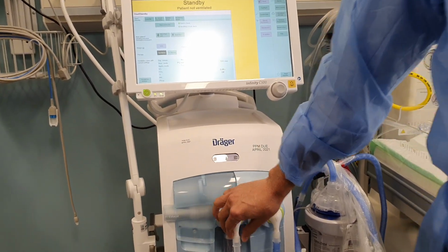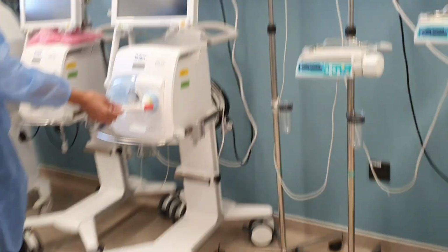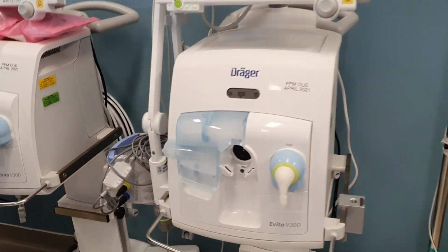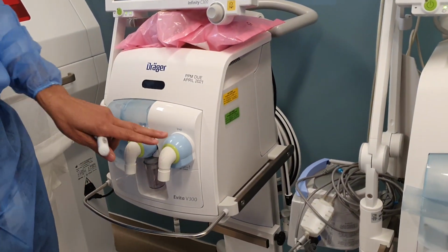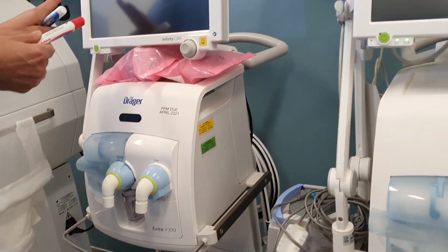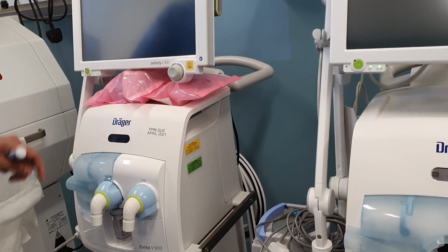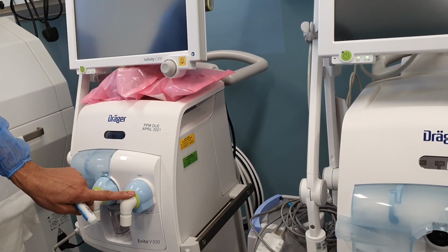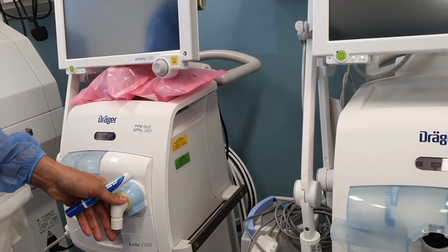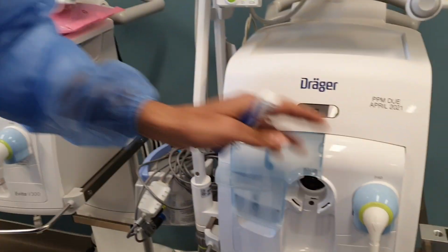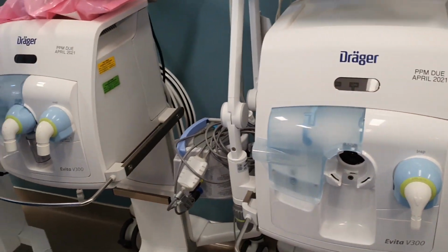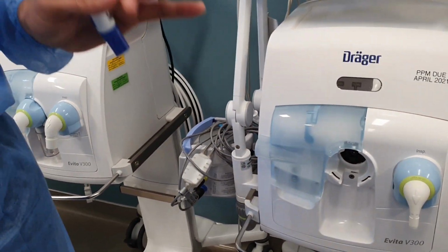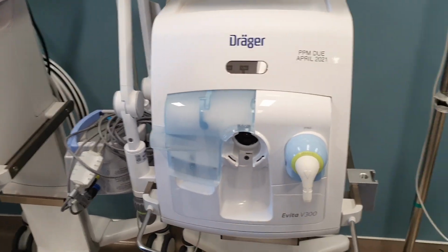If you see this one, this is neonatal. But this is adult. You see the difference? But this one can be used for neonates, but it will be dangerous, because if the software fails, it will give the adult type, so it can cause more injury. So we don't want a universal ventilator. We like to have a neonatal designated ventilator.